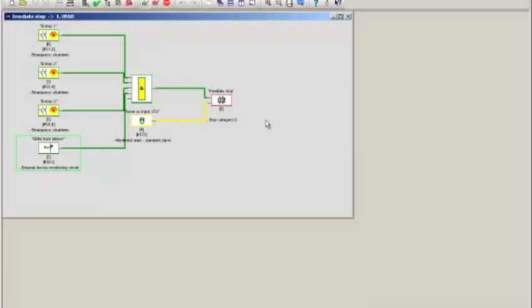So if I give the reset signal, which is applying plus 24 volts to pin S7-2, then everything will start up. Now again, EDM is a true signal, even though we know that the feedback circuit is open.